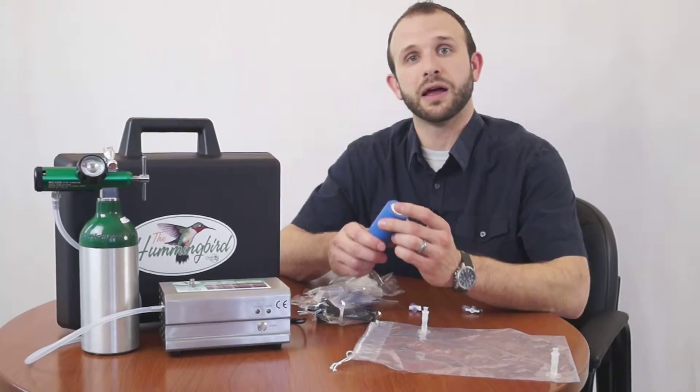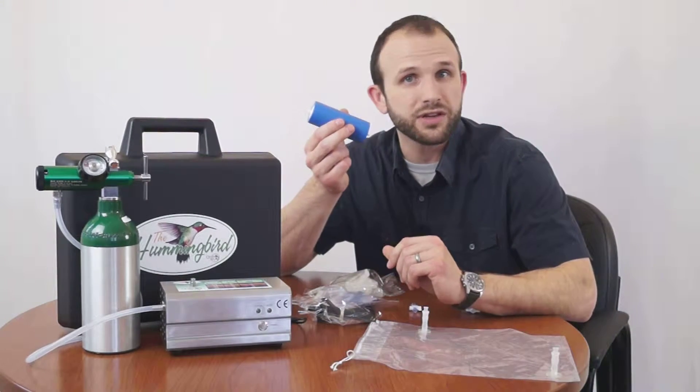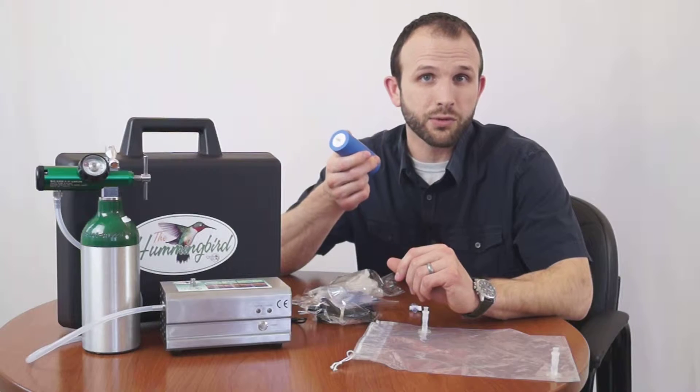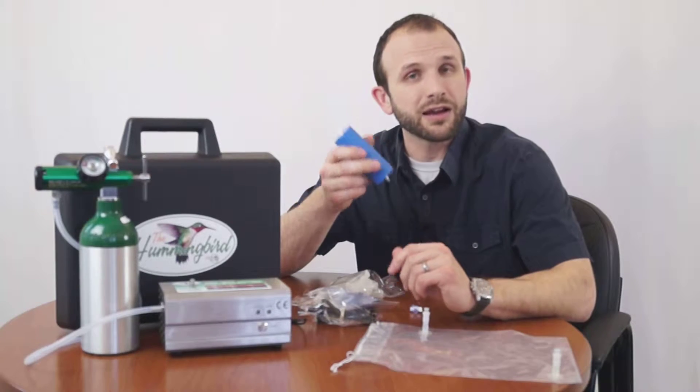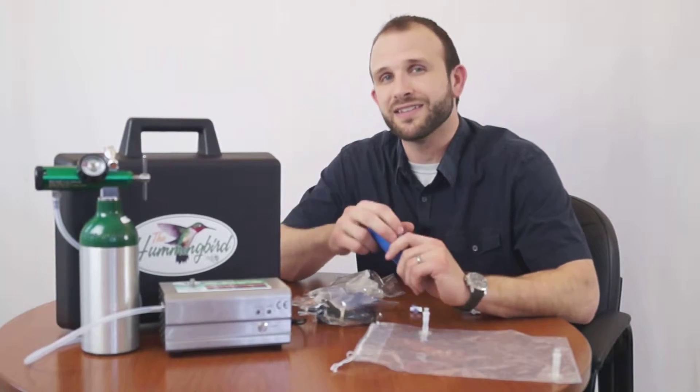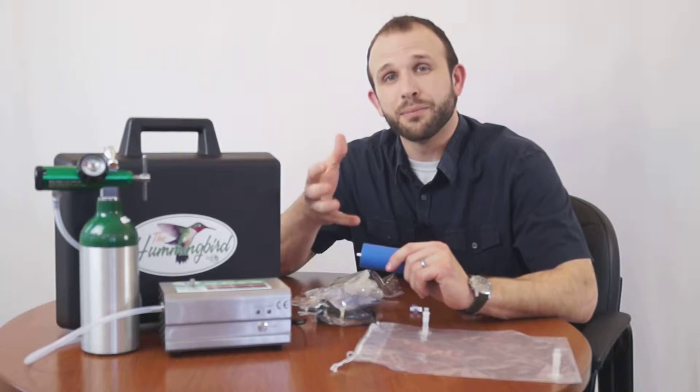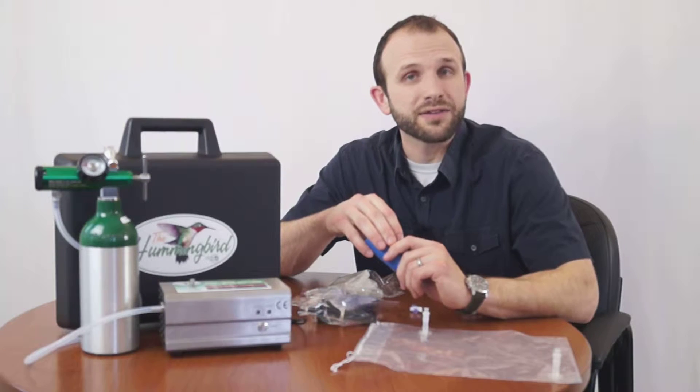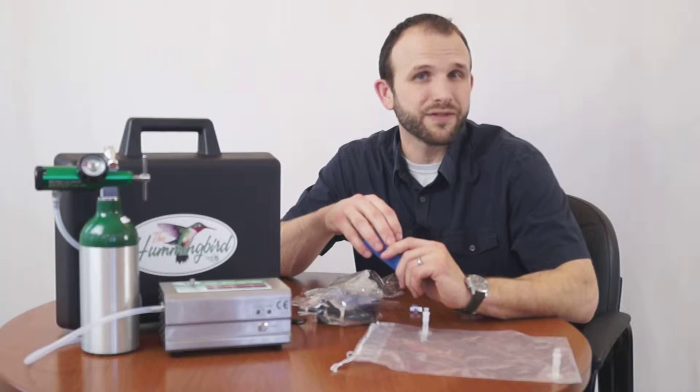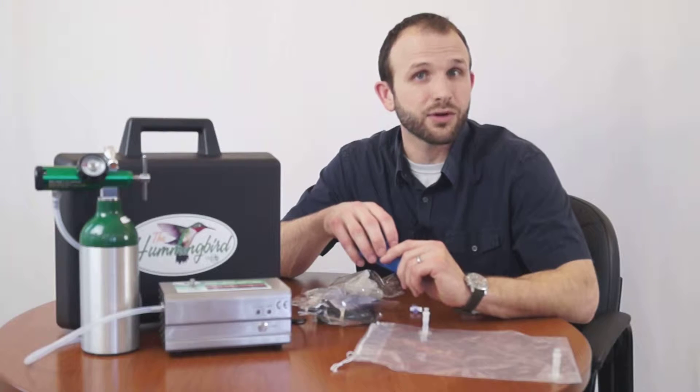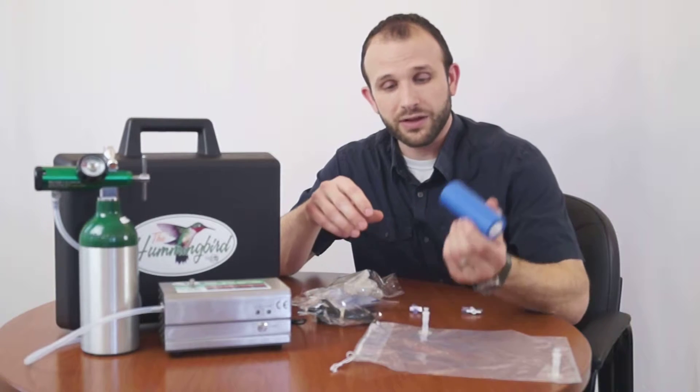What's a destruct? Well, that's what this is. This is what destroys unwanted ozone. When we're done with it, it's got to go out here. We don't like to just release all that into the air because breathing ozone can be hazardous to your health if you breathe too much of it and it's too high of a concentration.